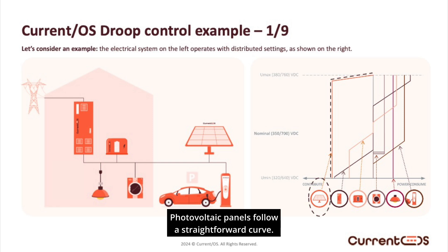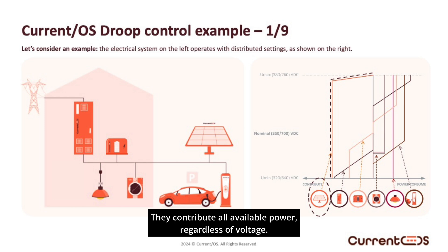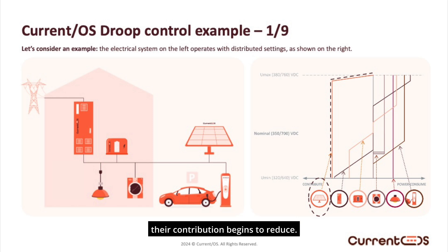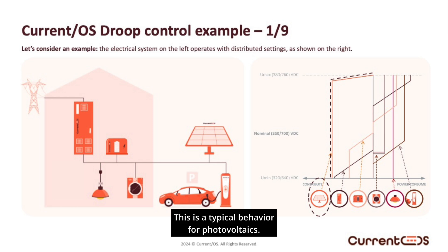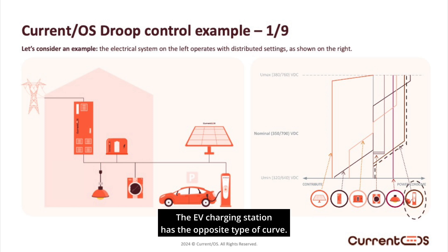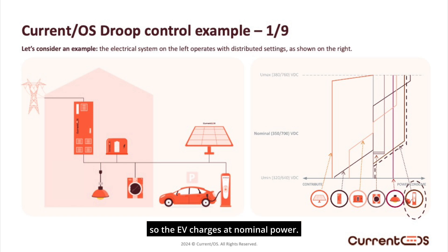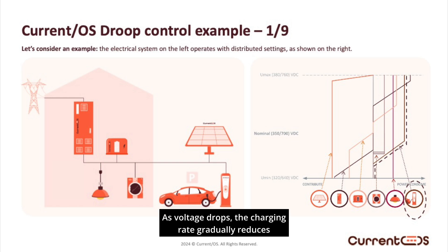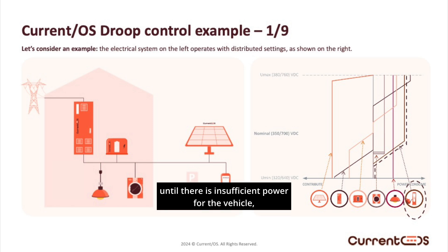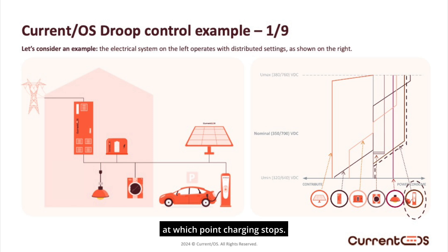Photovoltaic panels follow a straightforward curve. They contribute all available power regardless of voltage. However, when the voltage reaches a high threshold, their contribution begins to reduce — this is typical behavior for photovoltaics. The EV charging station has the opposite type of curve. High voltage signals that sufficient power is available, so the EV charges at nominal power. As voltage drops, the charging rate gradually reduces until there is insufficient power for the vehicle, at which point charging stops.